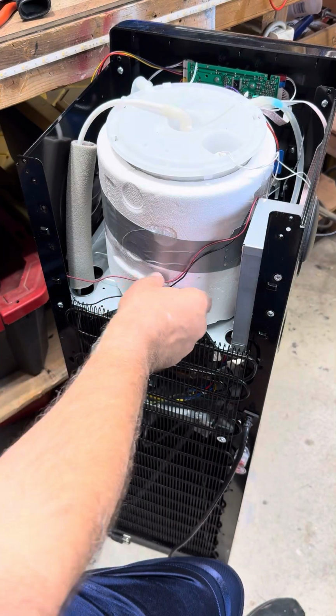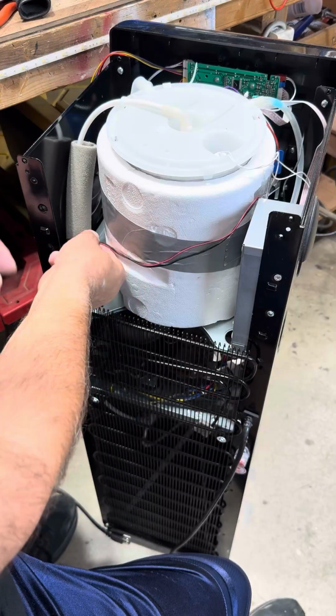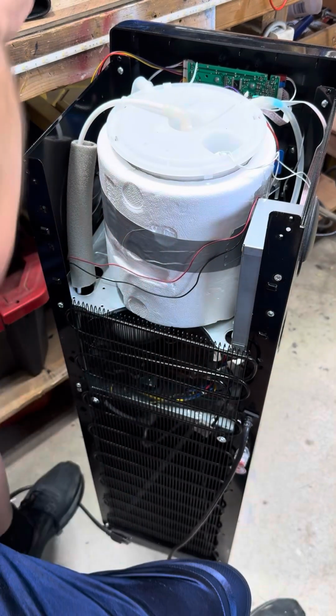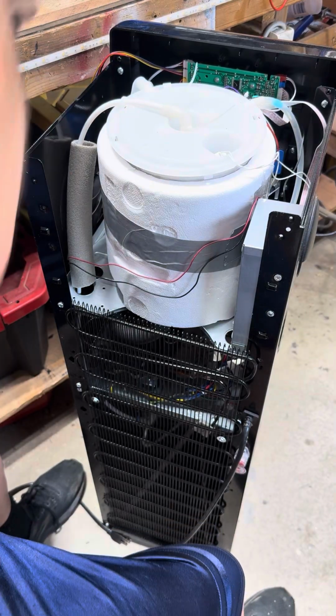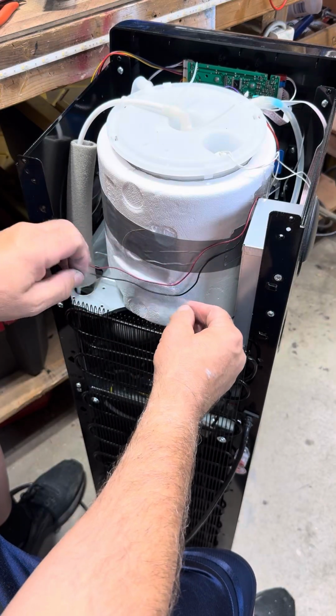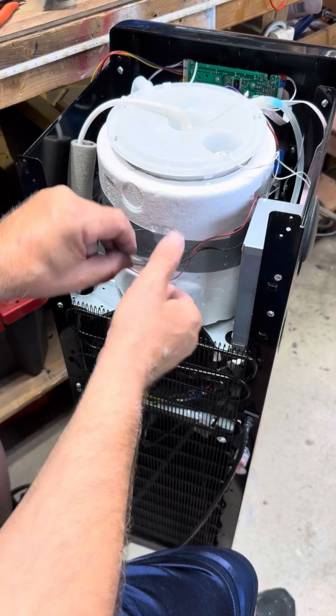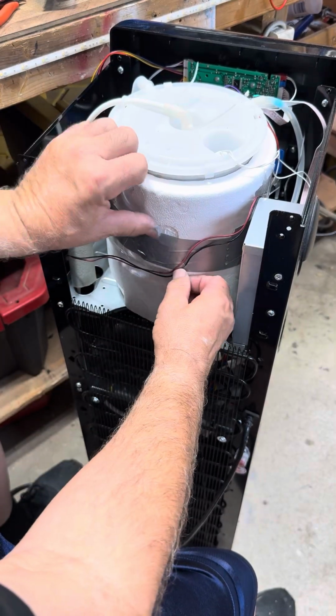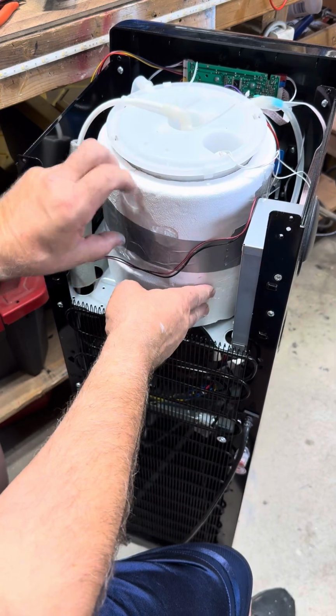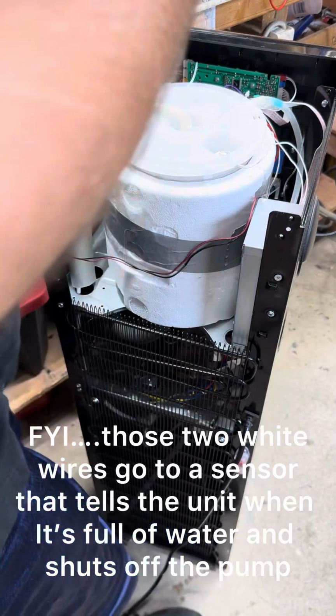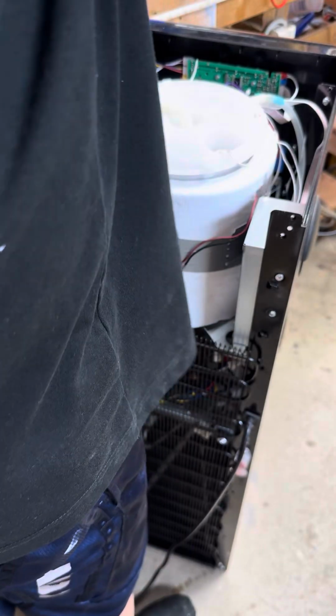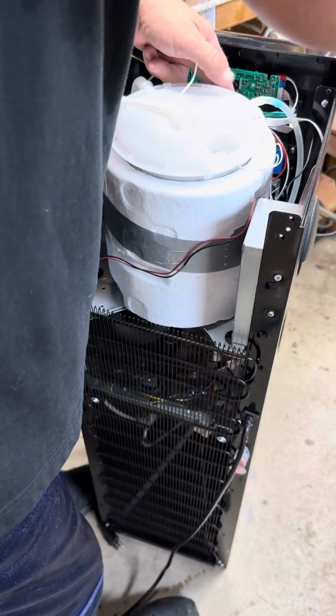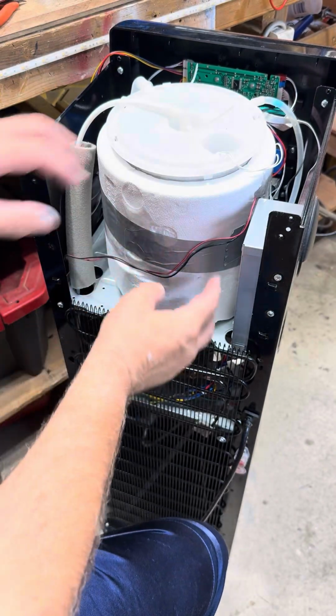Okay, very good. So again, let's double check wires. Very important that they don't get pinched during reassembly. You may want to take some small strips of pressure sealing tape, because when you took it apart, you probably noticed that your wires might have been taped to the side here, and it's good practice to go ahead and resecure your wires as they were when you took them apart. Check very carefully other ends, other edges. Being very careful. I'm going to reattach my wires here to the side chamber. Again, checking for no pinches, no obstructions. Everything looks pretty good. I like the way it looks.